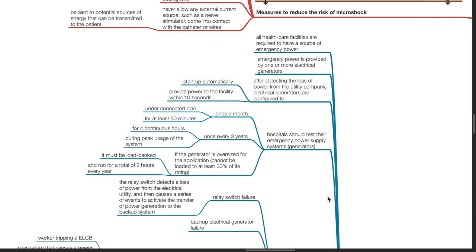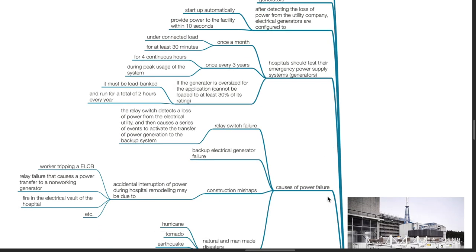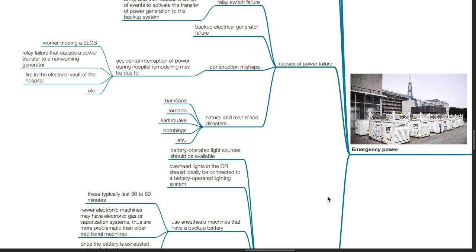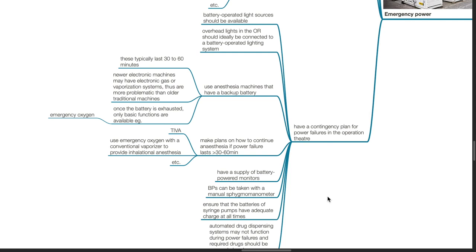Causes of power failure can be due to relay switch failure, backup electrical generator failure, construction mishaps, and natural and man-made disasters. Relay switch failure: The relay switch detects a loss of power from the electrical utility and then causes a series of events to activate the transfer of power generation to the backup system. Construction mishaps: Accidental interruption of power during hospital remodeling may be due to worker tripping an ELCB, relay failure that causes a power transfer to a non-working generator, fire in the electrical vault of the hospital, etc. Examples of disasters include hurricanes, tornadoes, earthquakes, and bombings.